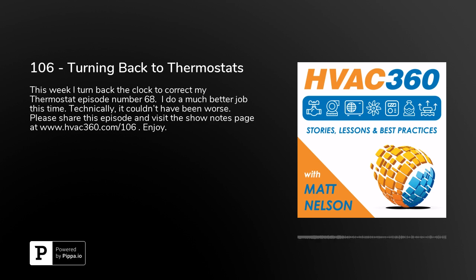For comfort, it's pretty easy, but when you deal with different applications, is the thermostat that you're selecting really specific for that application? Is it going to measure the right things? A lot of times we deal with thermostats with air, but there are also sensing things. If you're sensing water in a pipe, is it going to be the right temperature? A thermometer is a little bit easier to identify. But if you had a thermometer in a pipe that was measuring hot water, and your thermometer was from 0 to 100 degrees Fahrenheit, that's not going to be a great representation of the hot water, which needs to be more of a 50 to 250 range on the Fahrenheit scale. So you want to make sure that your application matches what you're doing.